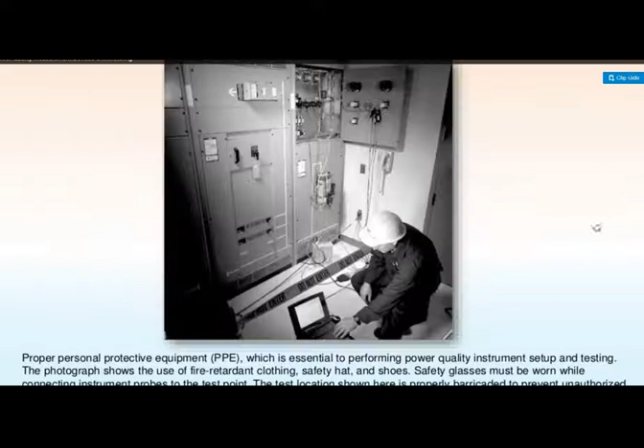The operator wears the proper equipment, like helmets and clothing. Proper personal protective equipment is essential to performing the power quality instrument setup and testing. The photograph shows the use of fire retardant clothing, safety hat and shoes. Safety glasses must be worn while connecting the instrument probes to the test point, and the test location shown here is properly barricaded to prevent unauthorized entry into this area.